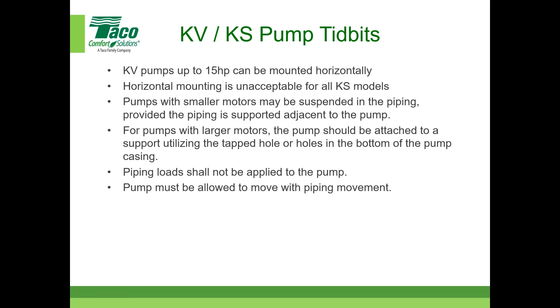Always start piping from the pump. I know it's difficult. A lot of times the piping is done first, and then you put the pump in and you have to line things up. The big screwdriver and the big crowbar aren't the way to a final alignment. So it really should start at the pump. I know that's a great statement for the manufacturer to make, but you need to take that into account somehow when things are being installed. You contractors out there, listen.